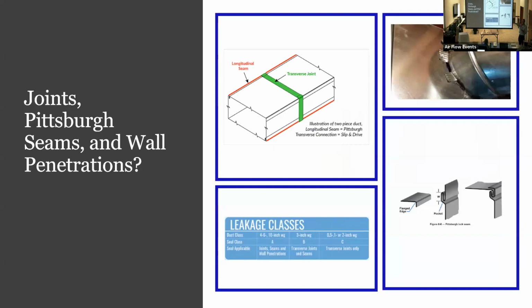it all the way around, the fourth side, we've got to fold it up. And that seam, the longitudinal seam, that's one thing. The transverse joint is another, and then when we put a hole in the duct, please don't do this, that's what the wall penetration is. So when we do seal class C, so everything on the low pressure side, the only thing that we need to do is this transverse joint.